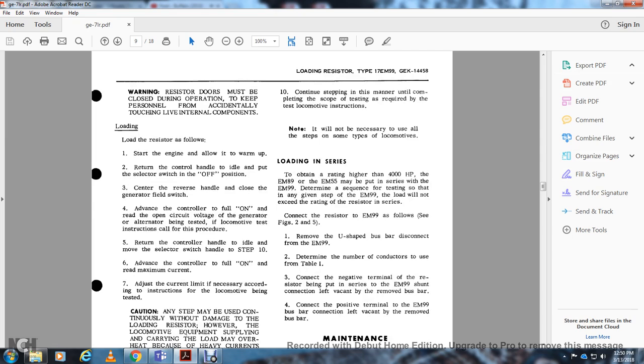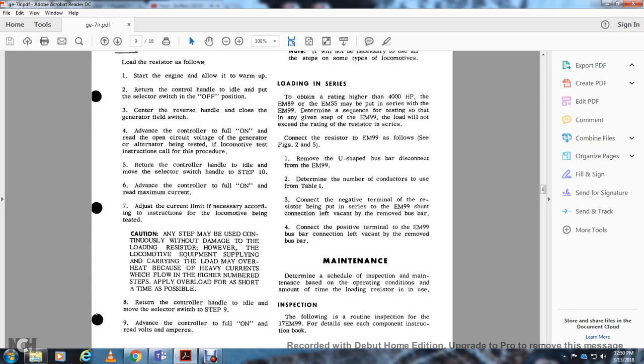Load the resistor as follows. Start the engine, allow it to warm up, return the control handle to idle, put the selector switch in the 'OFF' position, center the reverse handle, close the generator field switch, advance the control to the on position, and read the open circuit voltage of the generator alternator being used if the locomotive testing calls for the procedure. Return the control handle to idle, move the selector switch to step 10, advance the controller to full on, read maximum current, and adjust the current limit if necessary according to the instructions of the locomotive being tested.